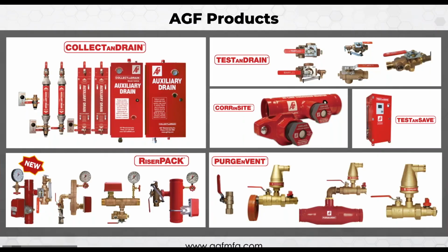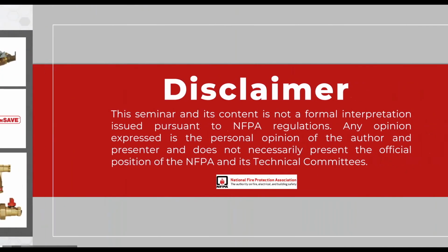For those of you who are, again, AGF isn't certainly rolling off the tongue as a familiar name, but the different products we make range from the test and drain valves, which if you go into the stairwells of almost any multi-story building built in the last 30 years around the world that has a fire sprinkler system, you would see these red-handled valves that say inspectors test on them, or main drain, or auxiliary drain, things like that. And my family is the one that makes a lot of these products. So from the test and drains to our air vents to collect and drains to riser packs, these are some of the different product lines that we manufacture.